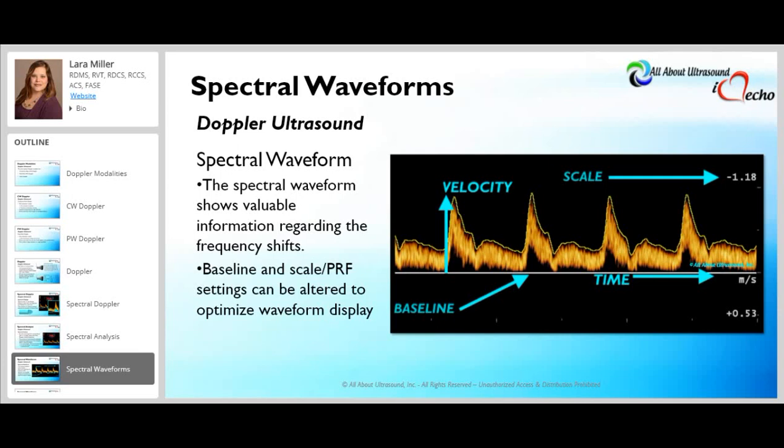We are able to see positive frequency shifts positioned above the baseline and negative frequency shifts positioned below the baseline. The baseline and scale settings can be altered to optimize the waveform display. There is also an invert control that may be used to display arterial waveforms above the baseline and venous waveforms below — but this does not necessarily indicate a positive or negative frequency shift, so all factors must be considered when interpreting the display.